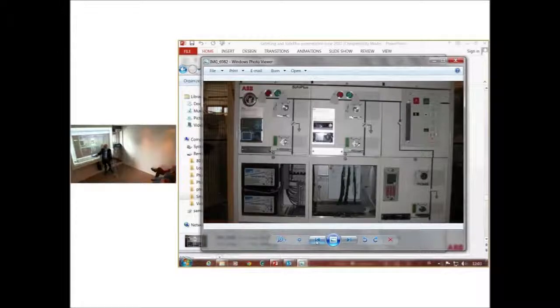If you have, let's say, your main supply here, you can use this capacitive device to measure if voltage is present. If the voltage disappears, both switches open, and we can program a mini PLC with logic. If this is the reserve, you can connect it. Let's say if this is the main supply and it fails, you connect to the reserve. If they both fail, you wait for whichever is coming back, and then you can have a time delay of 30 seconds before you connect it.